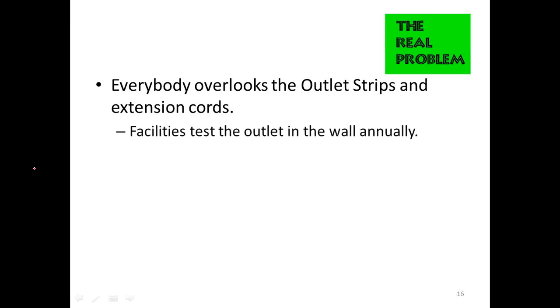We all know that facilities, the maintenance department, have a requirement to check all the electrical outlets in the hospital once a year. So they diligently go around with their tester, unplug something from the wall, plug in their little tester, and test the outlet. Once they've determined it's okay, they plug the plug back in without paying any attention to what it was — it could be patient care equipment, a television, or a multi-outlet strip.